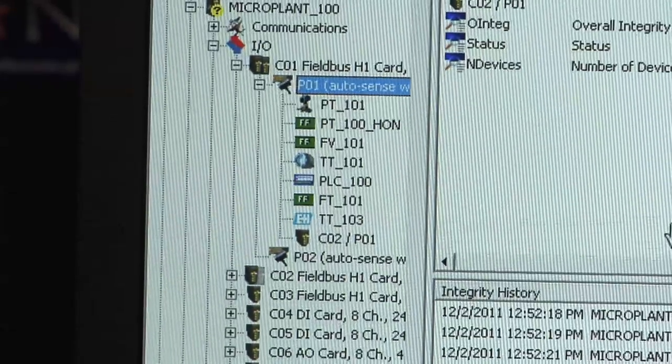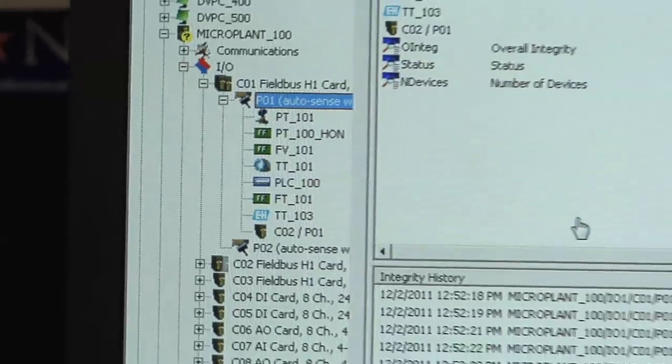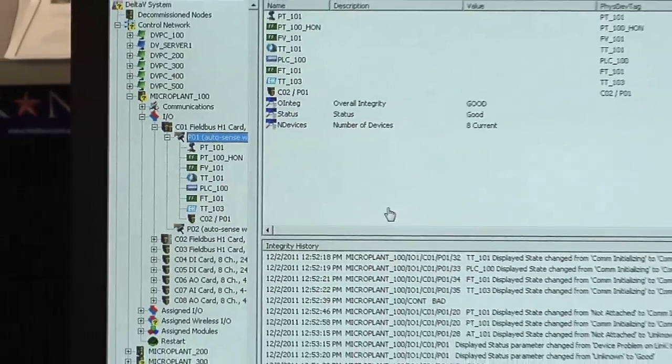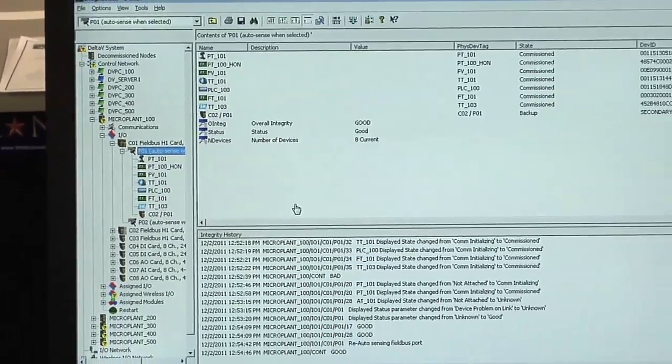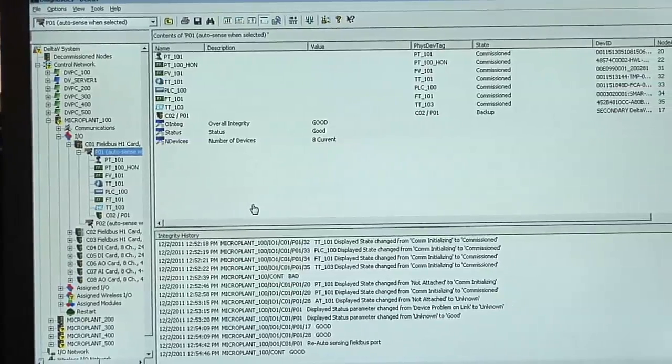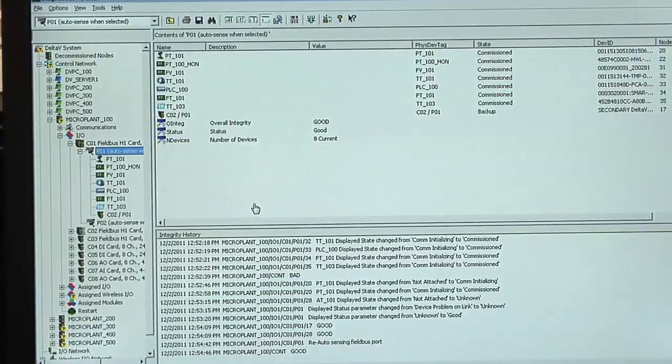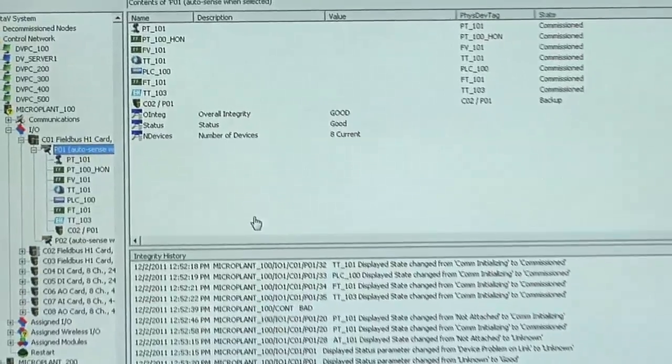Another possibility is somebody put it on a bench, and being very, very sensitive about addresses, because in many systems, if there's a conflict in addressing, it can cause serious consequences. So if that's the case, they may have said, well, let me give it an address while I work with it on the bench here, and I'll give it an address that I know nobody's going to use, but unfortunately, which is outside this first unpolled node range.